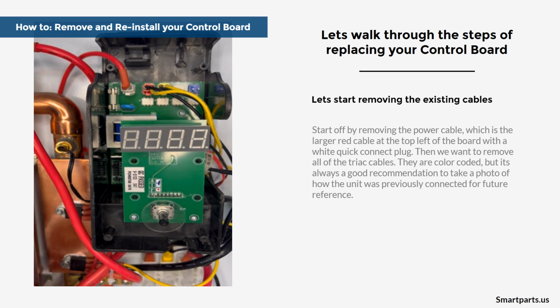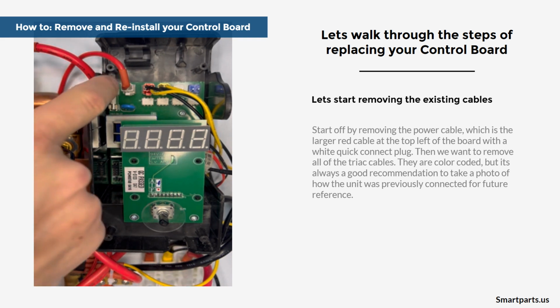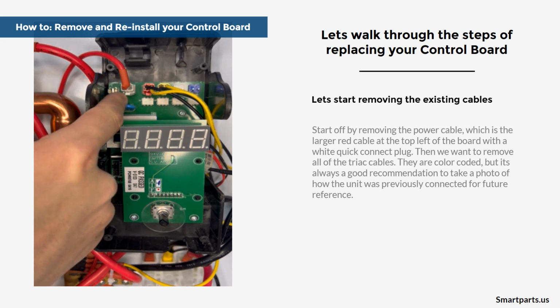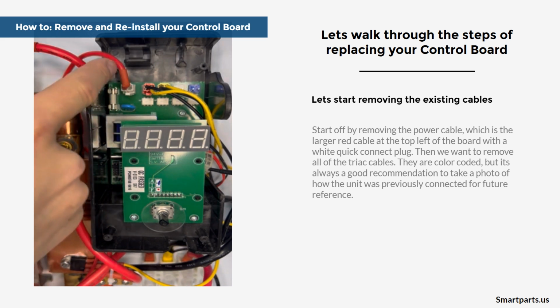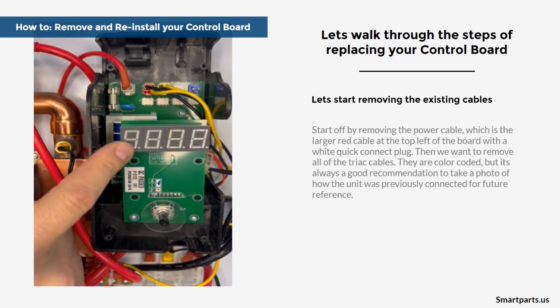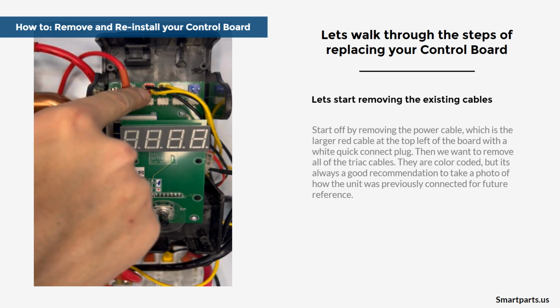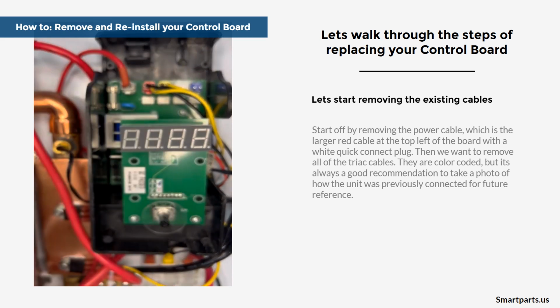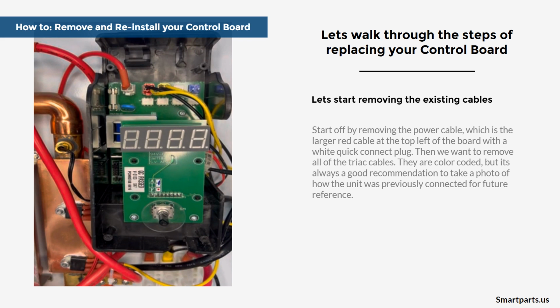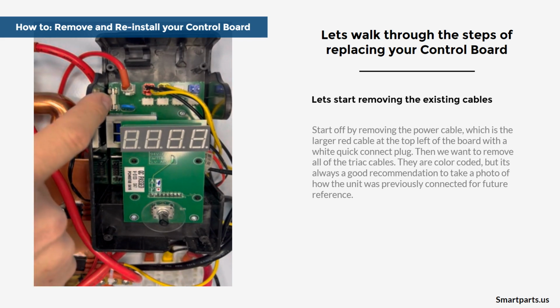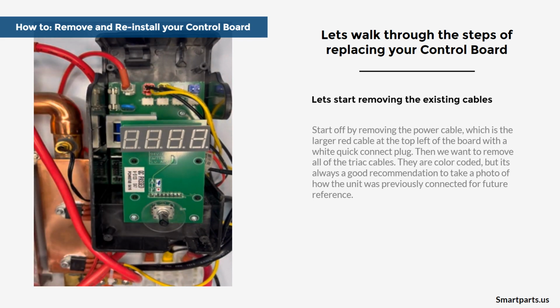As you can see with this unit here, we have our very first plug at the top left, this white quick connect here, with our large red cable. This is your power cable for the control board. Then over to the right, we have our red, yellow, white, and blue. Each one is specific for each triac. Red is for triac number 1, which is your first heating element. Yellow is triac number 2 for your second element. And as you can see, white is for number 3, and number 4 is your blue.